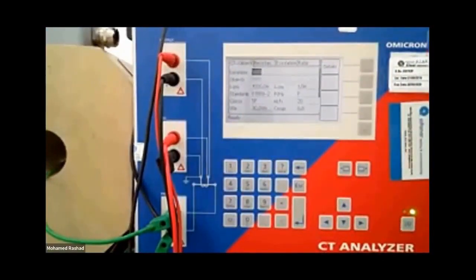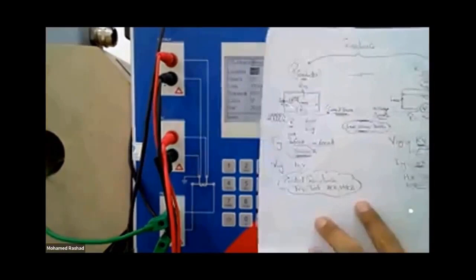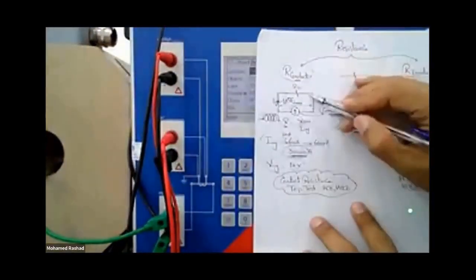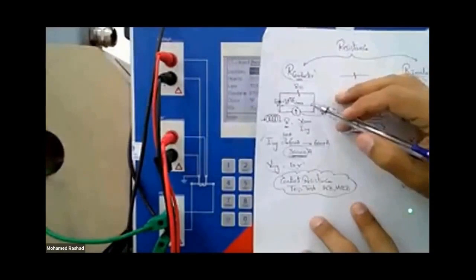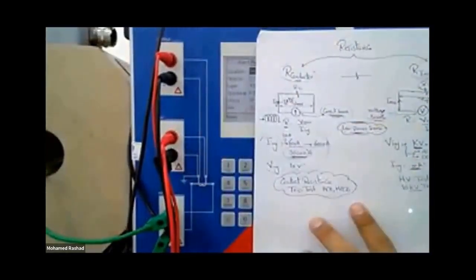The last thing you also need is what? It's the resistance of the coils, okay? And what do you want from the resistance of the coils? I want to inject current into it and measure the current correctly, right? So to inject current, what will you do? You also need the output generator to inject current from it and measure the current. Or for example, inject current from the secondary and measure the current through the output, exactly. Now, someone might ask, engineer, why didn't he just make a jumper from here to here and here to here?